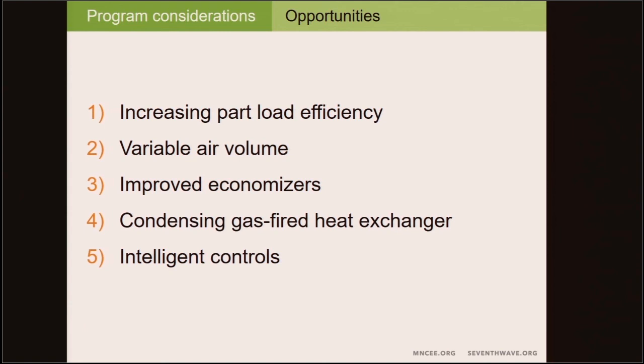Variable air volume capabilities, as opposed to the current standard constant volume systems, are becoming available on increasingly smaller capacities. Improved economizers ensure that the outdoor air dampers do not let in unconditioned air when closed. And advanced fault detection also ensures that the economizer is working properly. Condensing gas-fired heat exchangers capture the latent heat in the combustion exhaust, increasing the heating efficiency of gas-fired RTUs from 80% to approximately 90 to 95%. Increasingly, sophisticated intelligent controls are also being applied to RTUs. These controls are capable of precisely controlling RTU operation to optimize energy performance, as well as detect faults and alert maintenance staff to address degraded performance quickly.